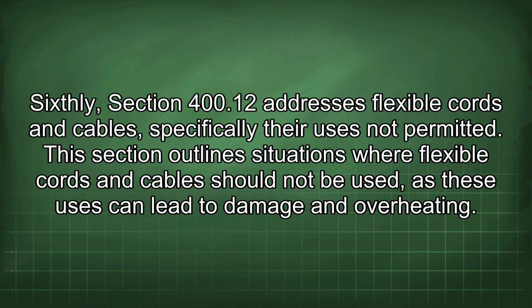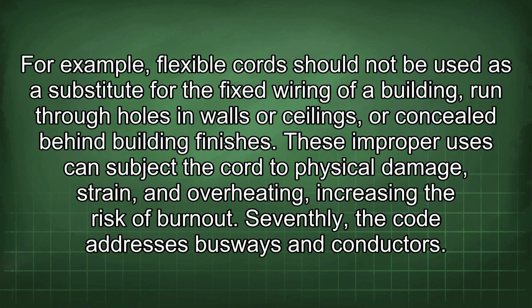Sixthly, Section 400.12 addresses flexible cords and cables. Specifically, their use is not permitted. This section outlines situations where flexible cords and cables should not be used, as these uses can lead to damage and overheating. For example, flexible cords should not be used as a substitute for the fixed wiring of a building, run through holes in walls or ceilings, or concealed behind building finishes. These improper uses can subject the cord to physical damage, strain, and overheating, increasing the risk of burnout.